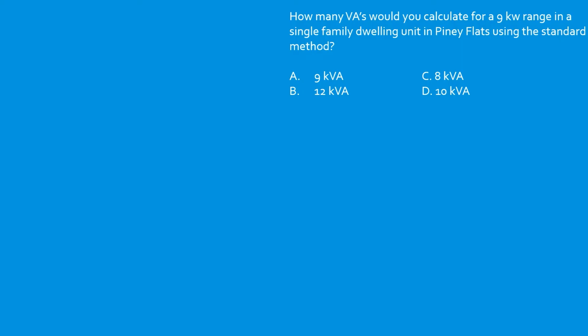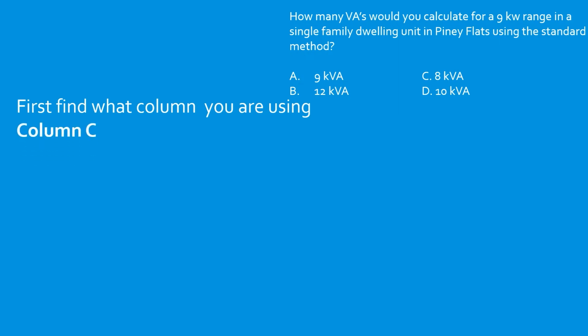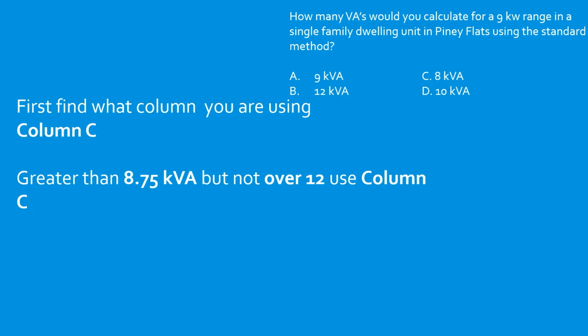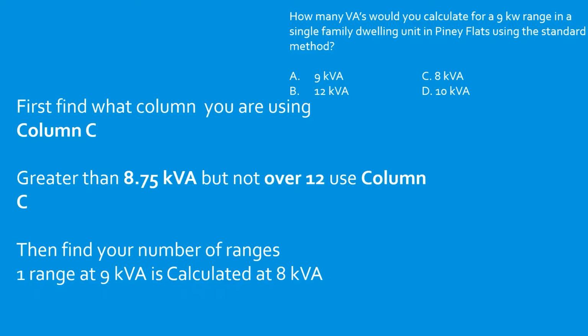All right, let's go ahead and answer our original question. How many VAs would you calculate for that 9 kW range? The first thing we're always going to ask ourselves with a range question is what column or columns are we using? In this case, we're going to be using column C because our range is rated more than 8 3/4, but not over 12. First thing we do is start on the left-hand side and find our number of ranges. Then we come over and tee off with our respective column, column C, and we select the replacement value, not a demand factor, for one range. In this case, it's going to be 8 kVA, and we would select C.